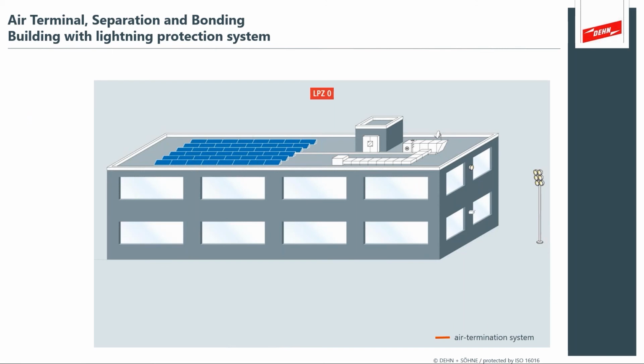So this illustration is nice because it shows you all of the factors all in play simultaneously. And we can look at the actual air termination system. You can follow the down conductors. You can see where the metal is bonded, and you can see where we can apply separation from victim equipment that you do not want to introduce lightning currents. You do not want to introduce side flash. You've got things like your solar panels that you separate from the air termination system. You've got things like a radio antenna that you separate. You've got security cameras, light pole cameras, Wi-Fi transmitters and radios that you want to separate from your lightning protection system.